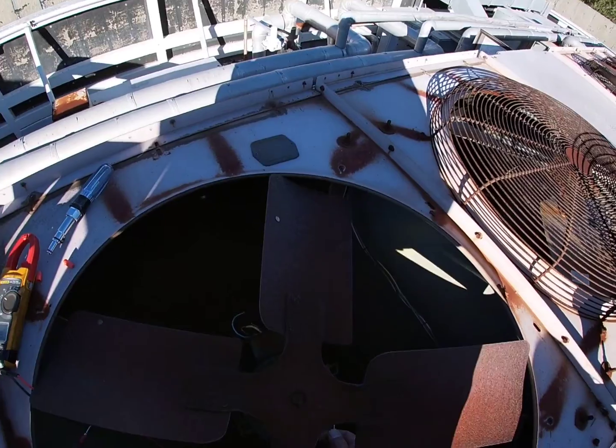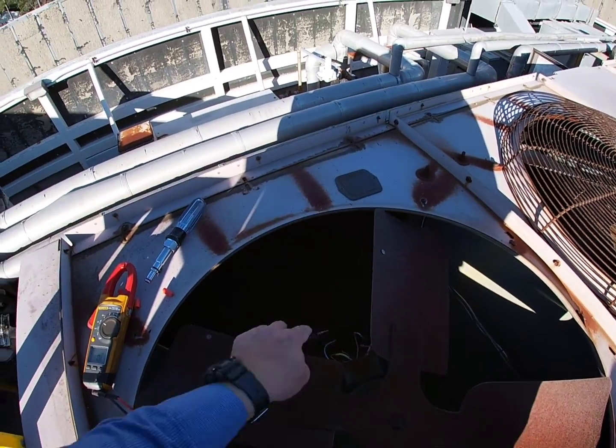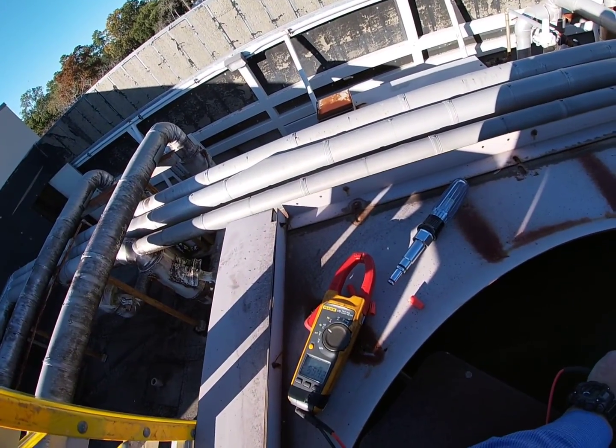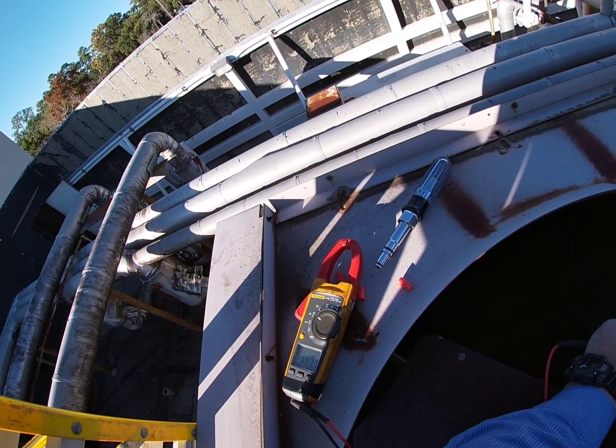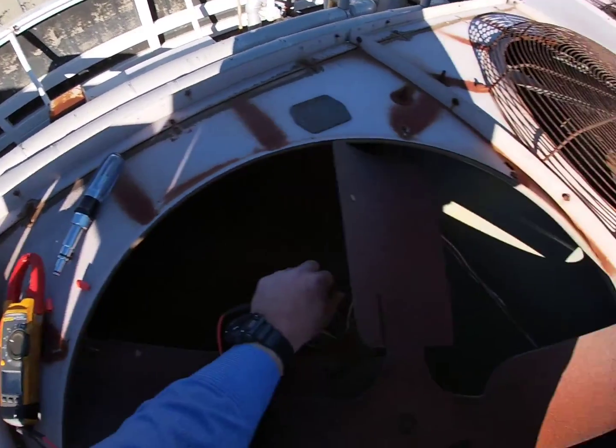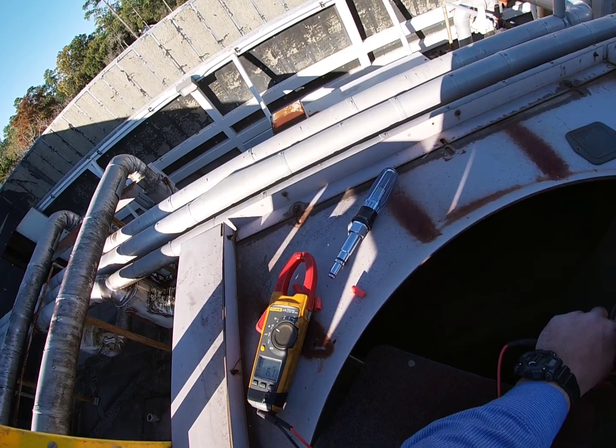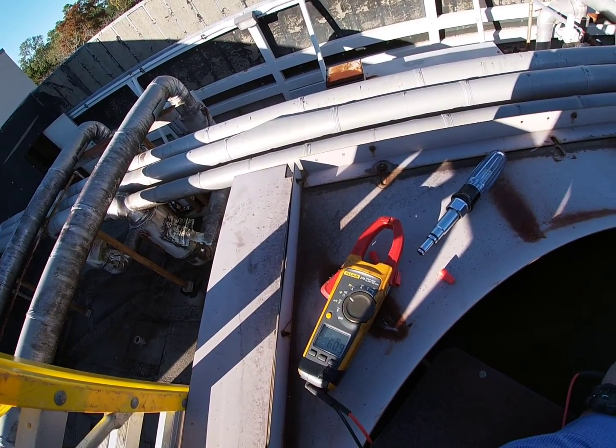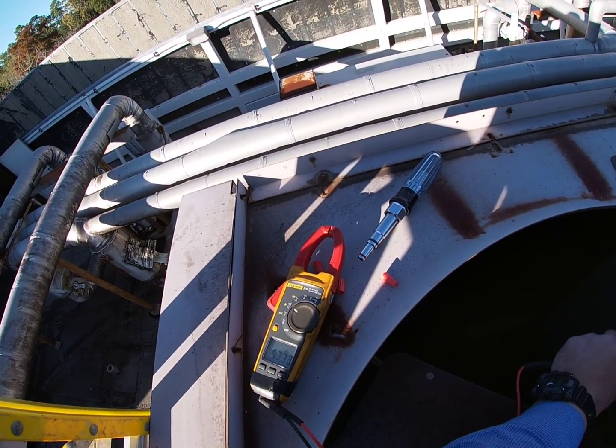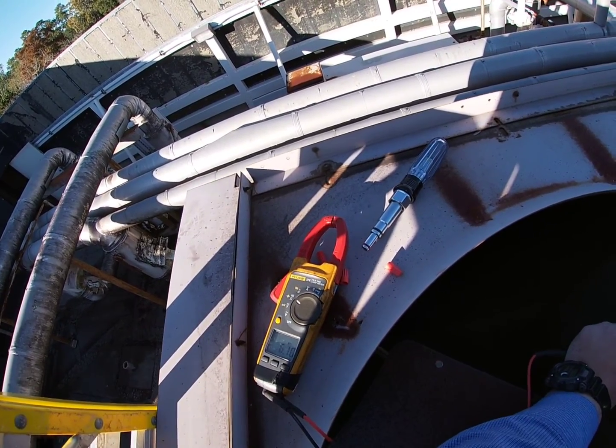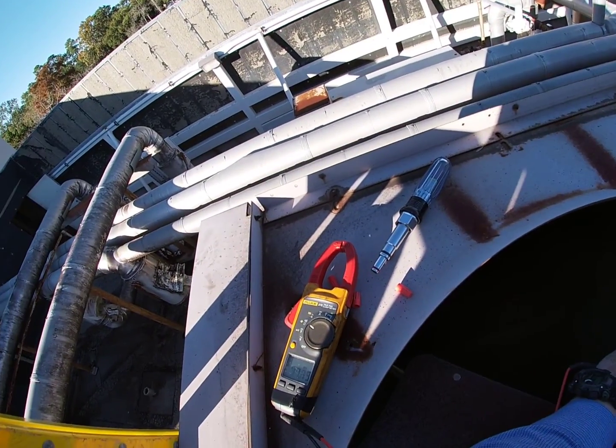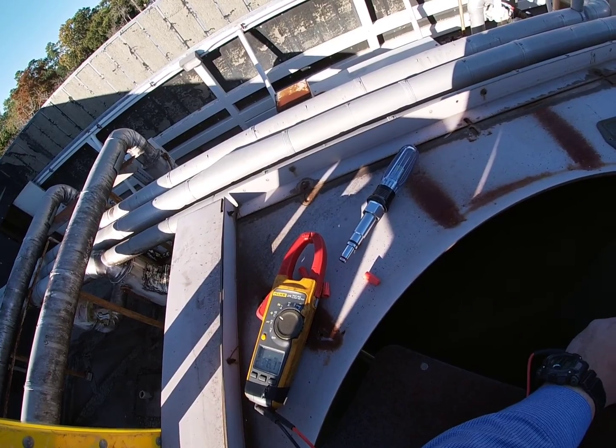Now let's find a good ground source here on this motor. Yeah, it's a bad motor. Saw it pop up there. Can't get a good ground though, but there it goes. 6K ohms to ground, so that is a bad motor.